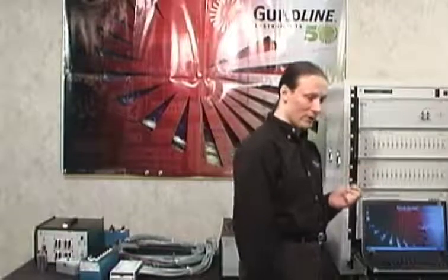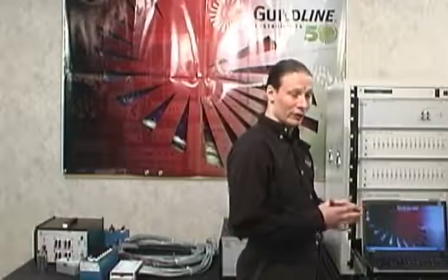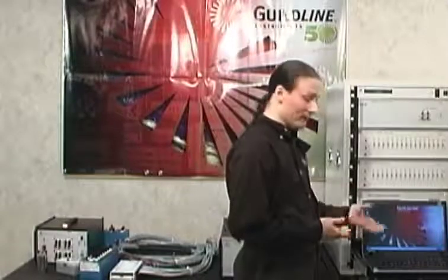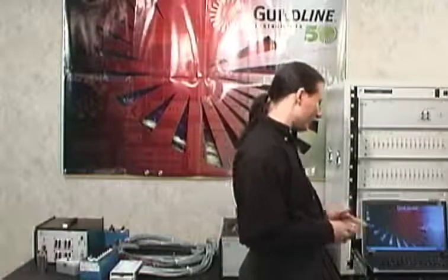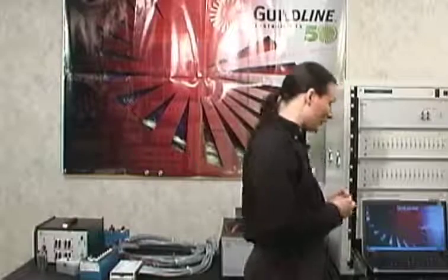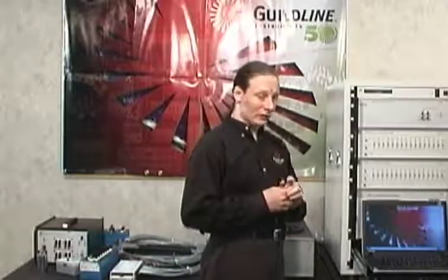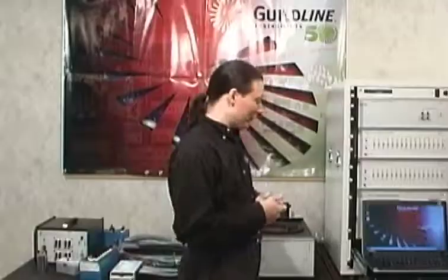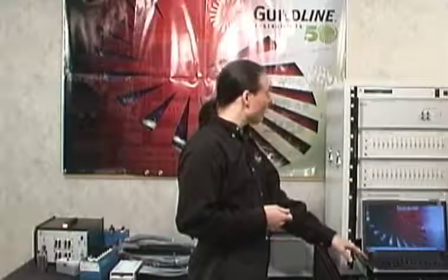To install the software, it comes provided on a single installation DVD, and you just put the software into the CD-ROM and the auto run kicks up automatically and just goes ahead and starts installing. So it's quite simple. The software communicates through an IEEE interface. National Instruments creates this device, and it's more commonly known as the General Purpose Information Bus, or GPIB. This is connected through USB in the back of the laptop, and it's connected to the back of the rack through all the devices that are running.